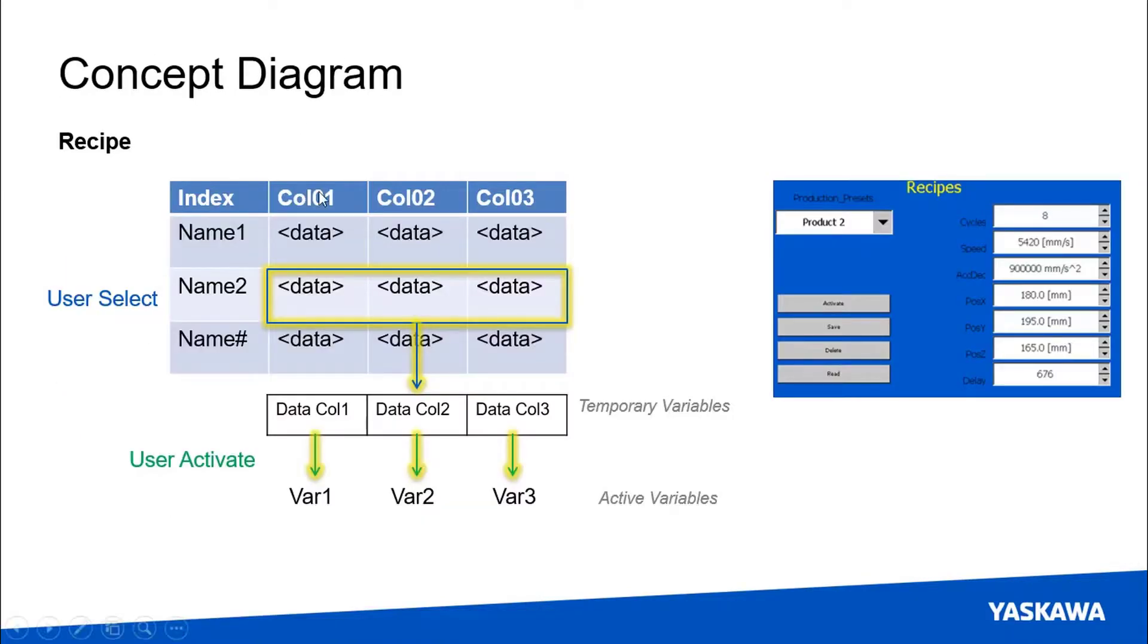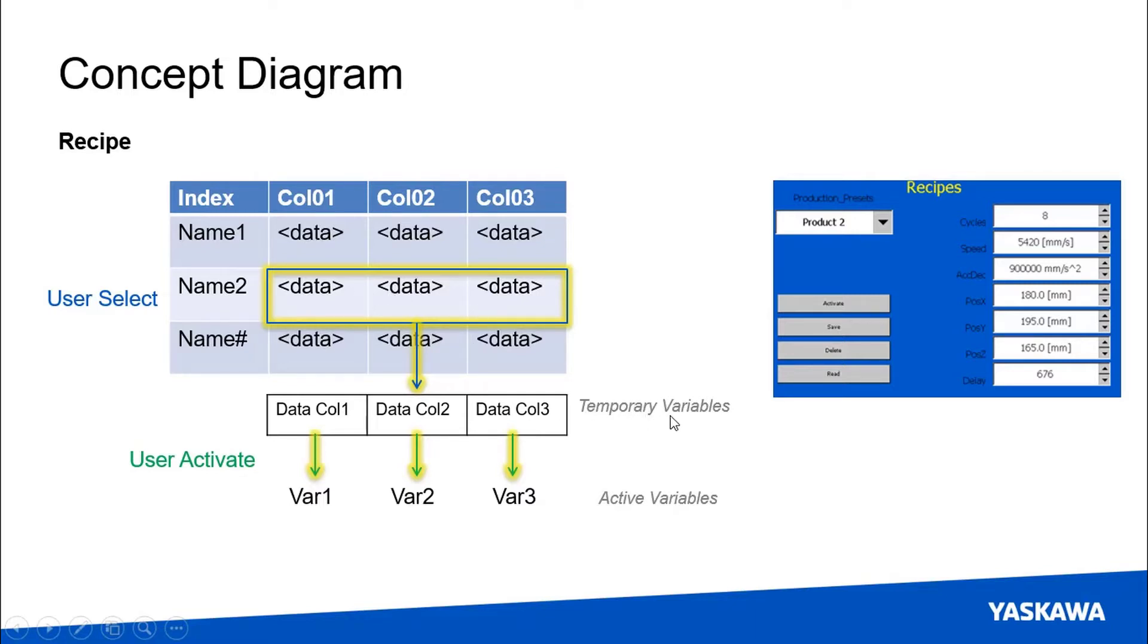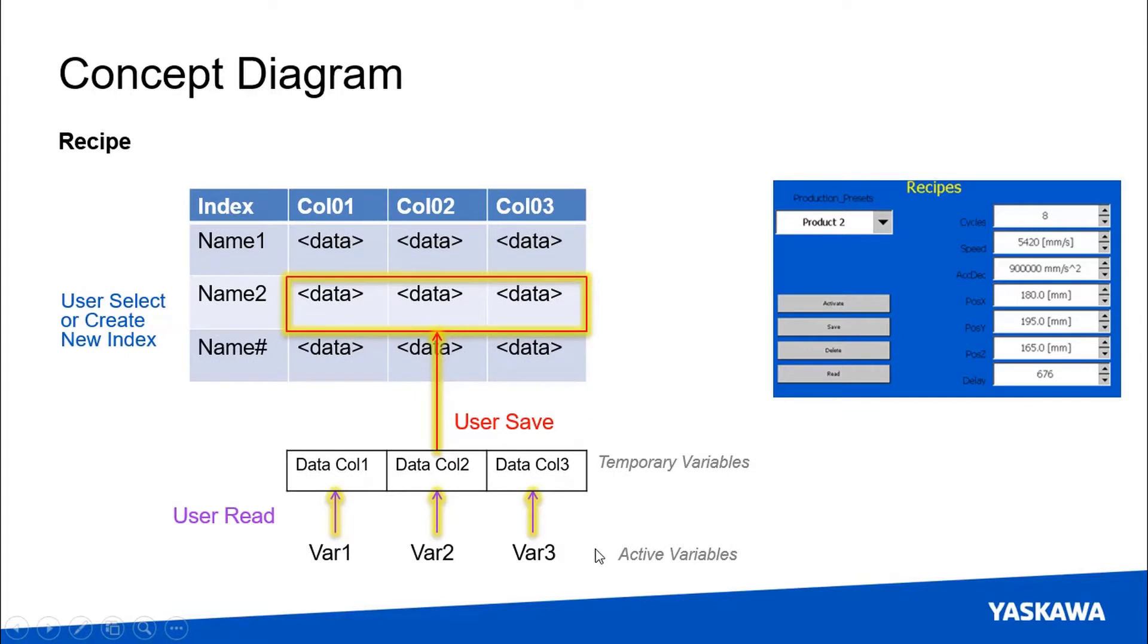Another way to look at it conceptually is that each of the recipes you saw me choose can be thought of as a row in a spreadsheet and they call that the index. You saw me the user selecting the different names of these recipes and even entering new ones. Whichever one of those recipes is selected is the one that will be shown in that temporary variable area and the activate command loads them into the active variables.